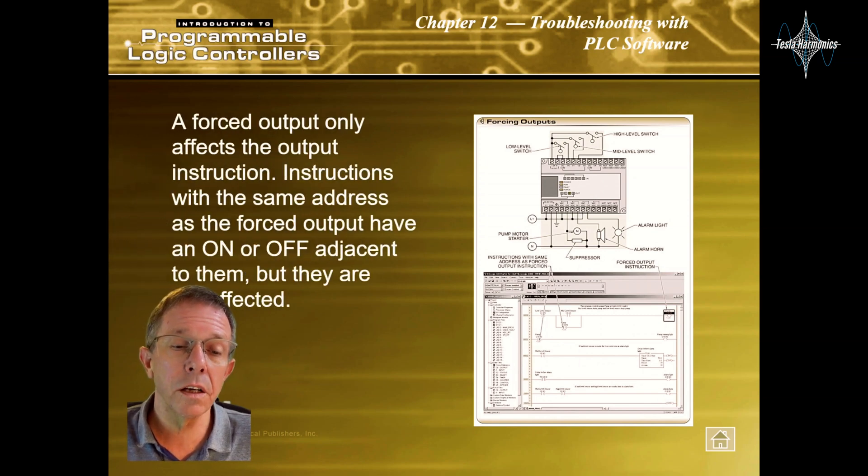A force output only affects the output instructions. Instructions with the same address as the force output have an on or off adjacent to them, but they are not affected.